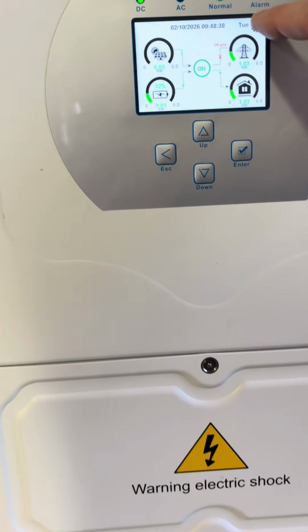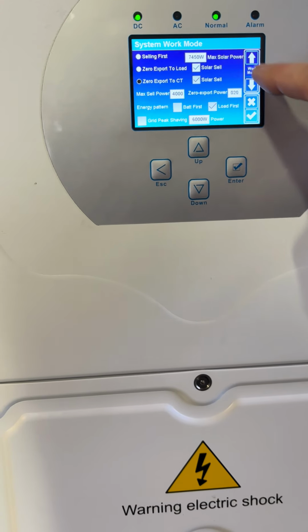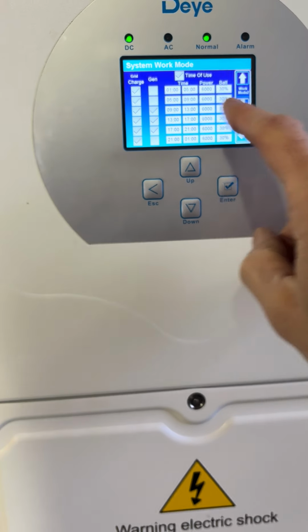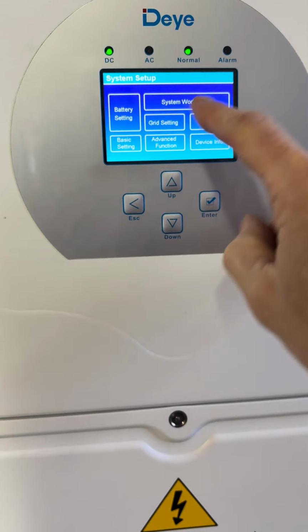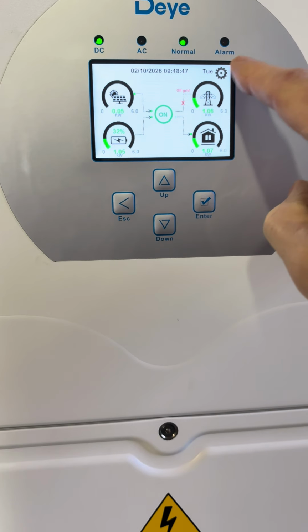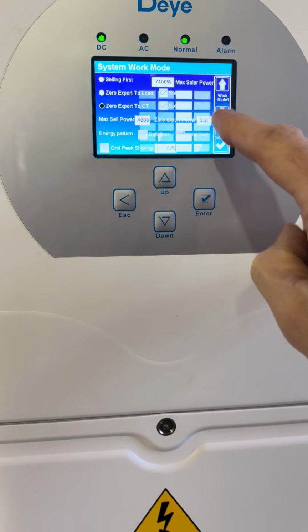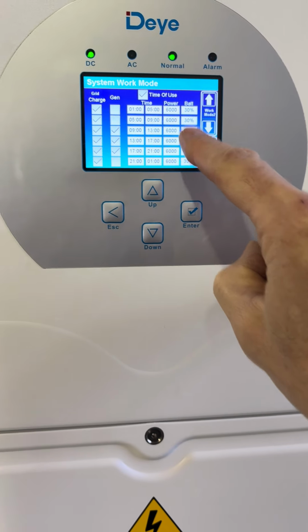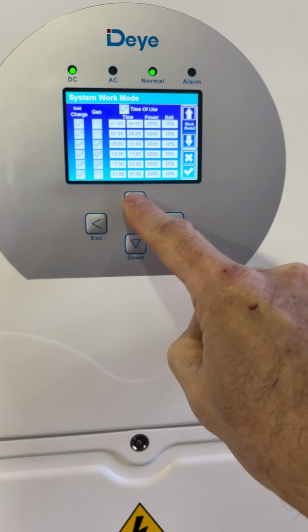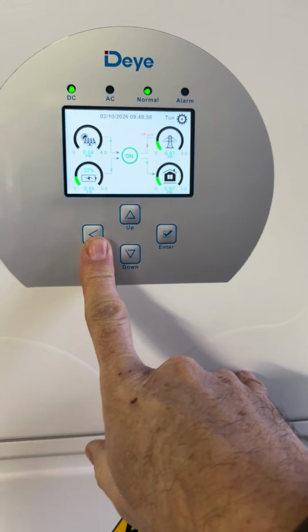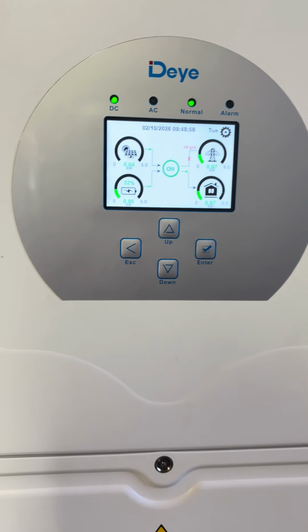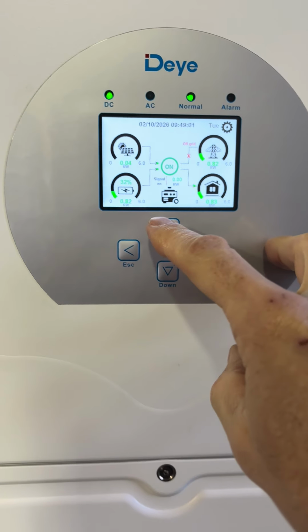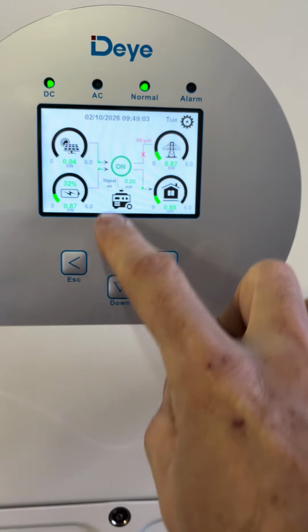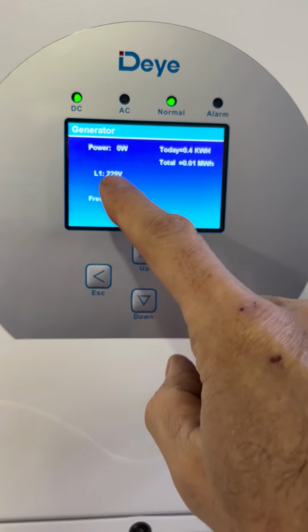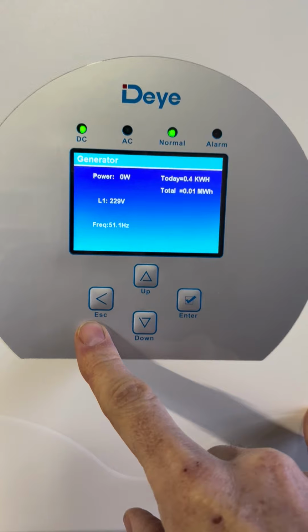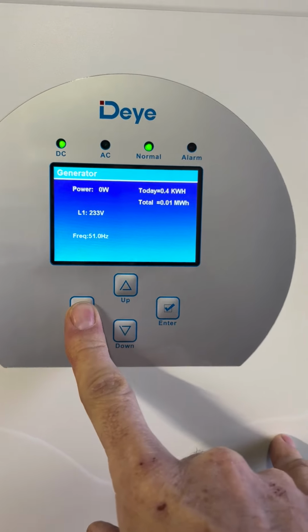Now, in order to get the diesel generator to come in, we go to system work mode. The time of day now is 9:48 AM. System work mode 9. If I increase my battery capacity there to greater than what we're at, that will now tell the generator to come on. Okay, we can see that. And we can see our generator is holding 230 volts, 51.1 hertz.